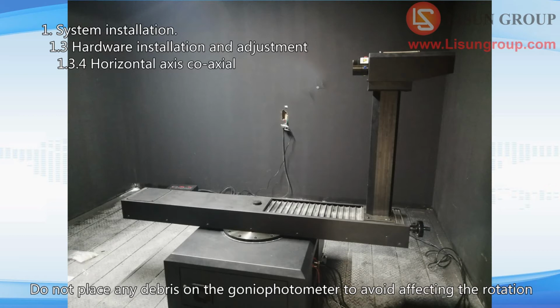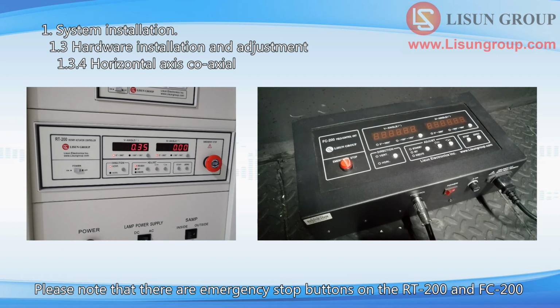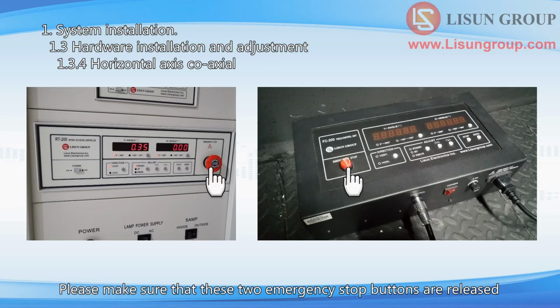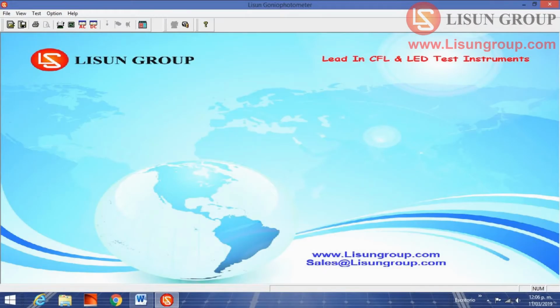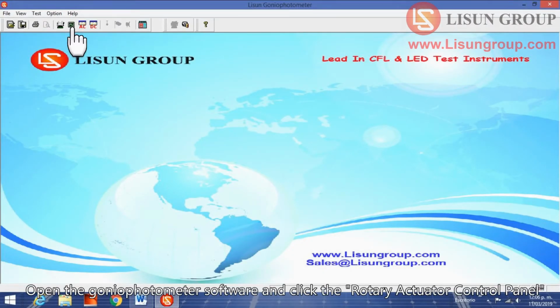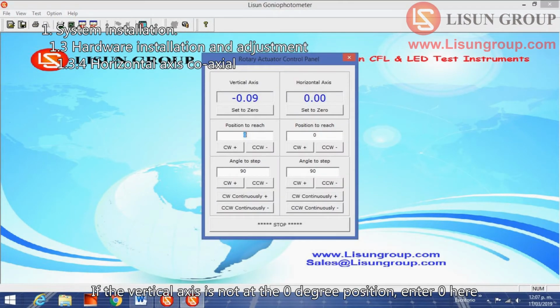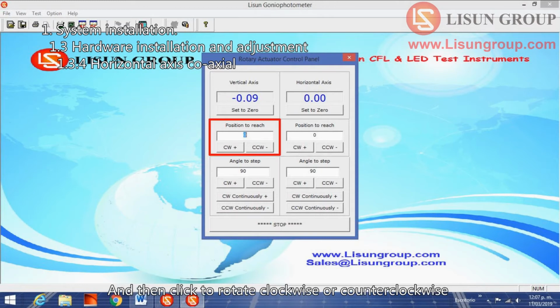Do not place any debris on the goniophotometer to avoid affecting the rotation. Please note that there are emergency stop buttons on the RT200 and FC200. Please make sure that these two emergency stop buttons are released before you operate the goniophotometer. Open the goniophotometer software and click the rotary actuator control panel. If the vertical axis is not at the 0 degree position, enter 0 here and then click to rotate clockwise or counterclockwise to rotate the vertical axis to the 0 degree position.